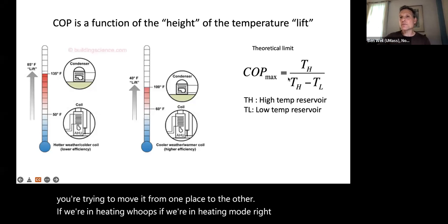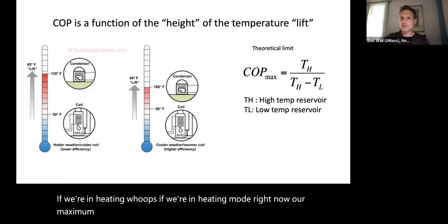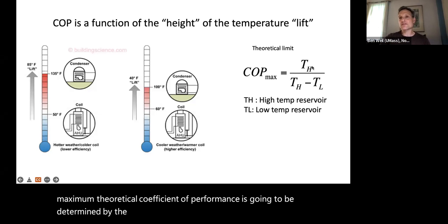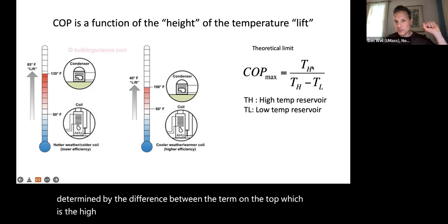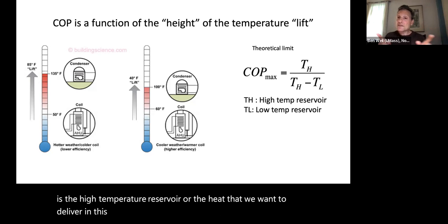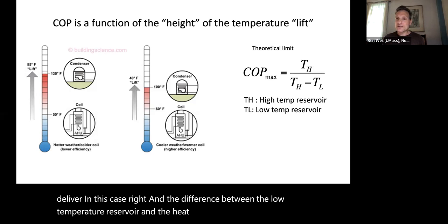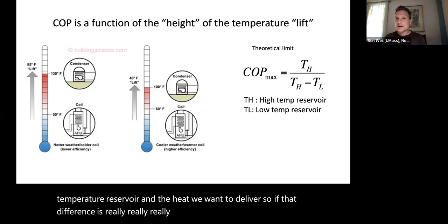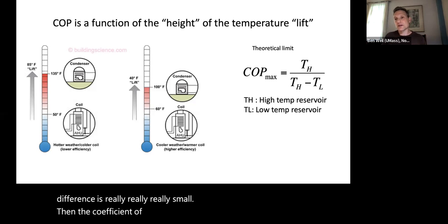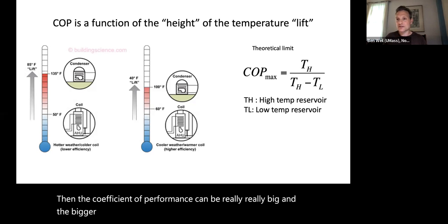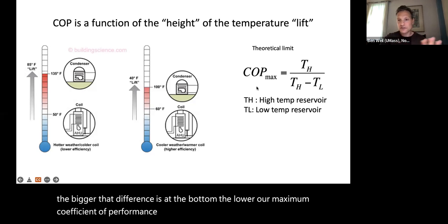If we're in heating mode right now, our maximum theoretical coefficient of performance is going to be determined by the term on the top, which is the high temperature reservoir, or the heat that we want to deliver in this case, and the difference between the low temperature reservoir and the heat we want to deliver. So if that difference is really, really small, then the coefficient of performance can be really big. And the bigger that difference at the bottom is, the lower our maximum coefficient of performance can be, regardless of everything else we do.